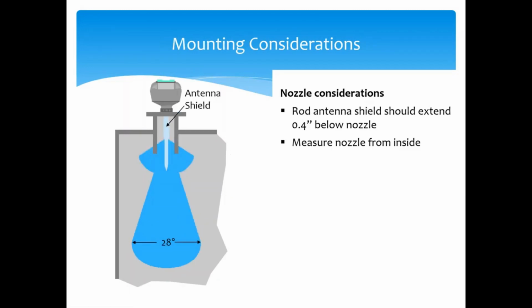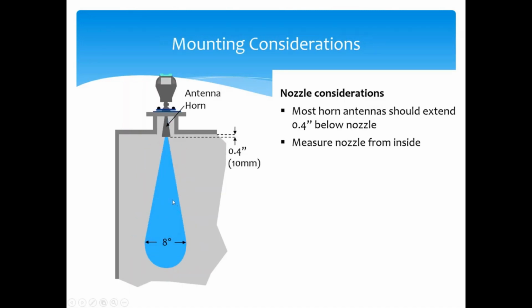The other thing to point out on this slide is that with these rod style antennas, the beam angle, or the shape of that beam, is as you see here, where it's wider right up at the top and then has more of a teardrop shape below that, compared to your horned radars, where it comes out in a conical shape like you see here, or a teardrop shape.